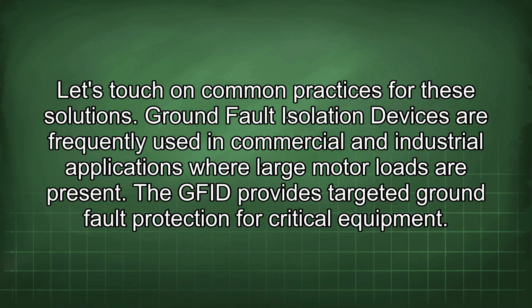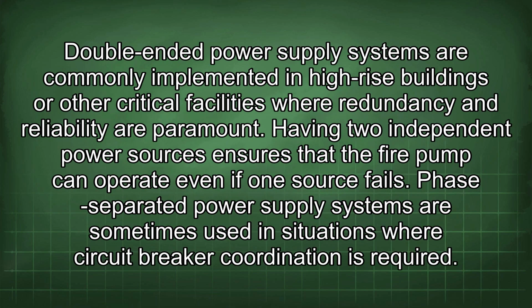Let's touch on common practices for these solutions. Ground fault isolation devices are frequently used in commercial and industrial applications where large motor loads are present. The GFID provides targeted ground fault protection for critical equipment. Double-ended power supply systems are commonly implemented in high-rise buildings or other critical facilities where redundancy and reliability are paramount. Having two independent power sources ensures that the fire pump can operate even if one source fails.